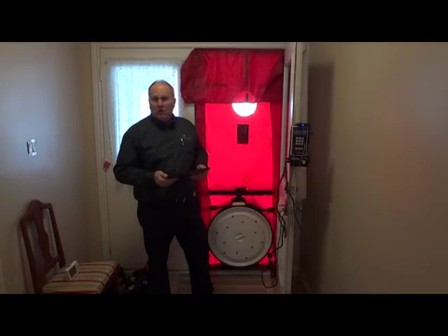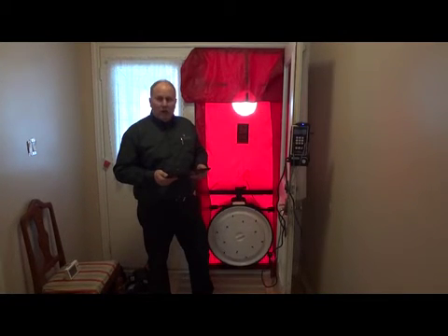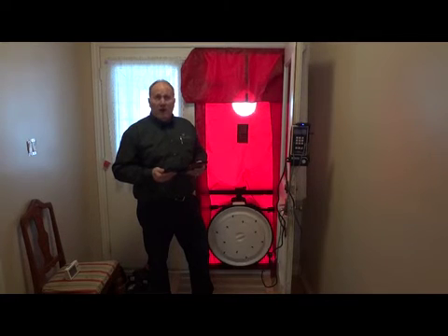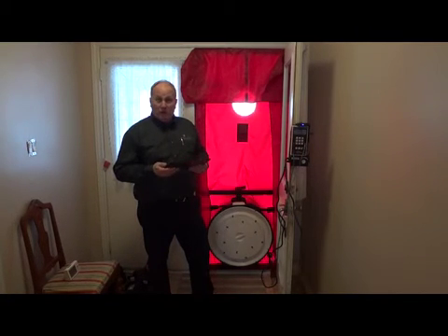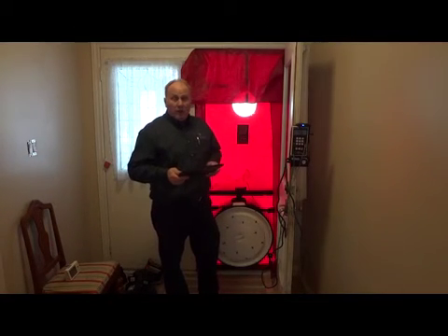Okay, according to our blower door test, Tom has a very tight home. The air exchange, or ACH 50, that we just measured came in at less than 3, which in my experience in doing thousands of these assessments, ranges anywhere from 4 to 20. Tom is sub 3, so he's done very well. That means his house experiences 3 air exchanges per hour on average. Congratulations to Tom for doing the weatherization and tightening things up and building a nice tight house.